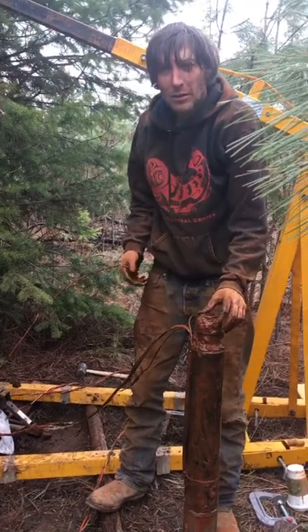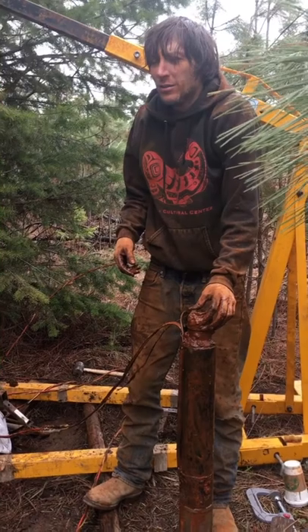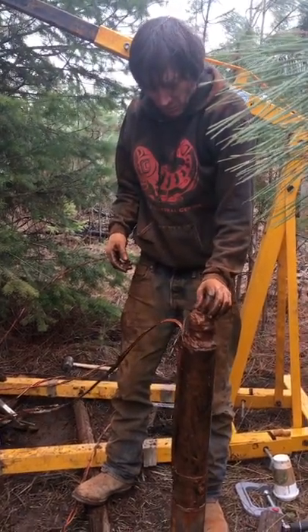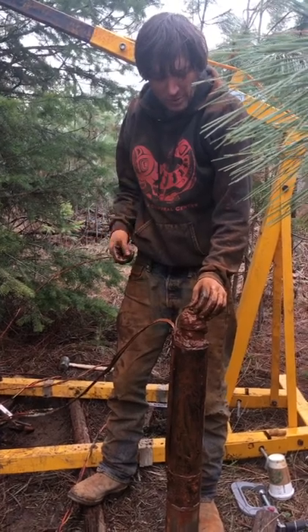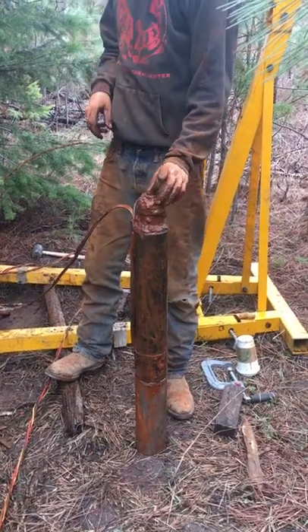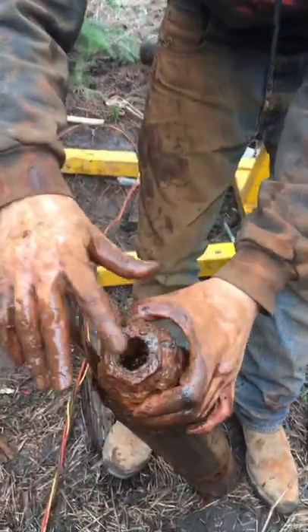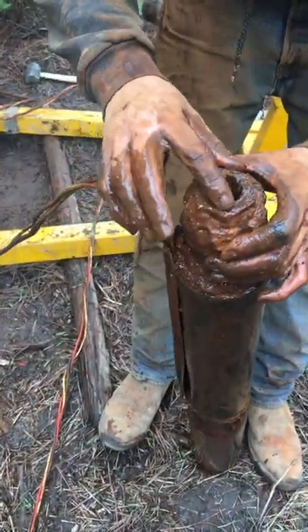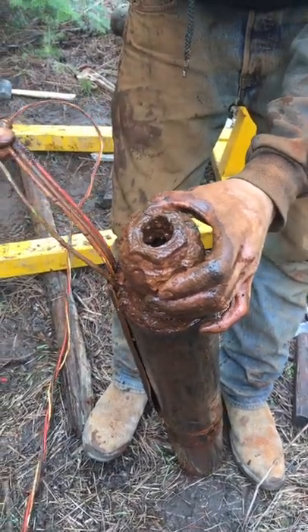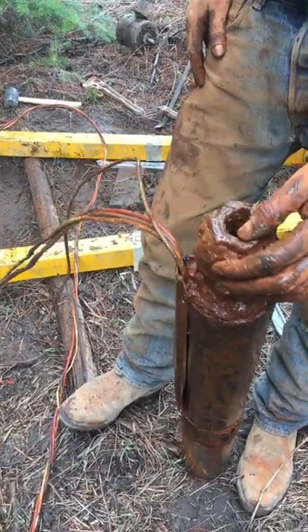Got the pump out. It actually ended up being 360 feet of pipe, and I'm not sure of the actual state of the pump. It just quit working. When we pulled it up, the threaded part of the pipe is still in here, and this was broken. You can tell it's been broken for some time. It was basically held on by these wires taped to the rest of the pipe — it's not bringing it up that broke it, it was already pre-broke.